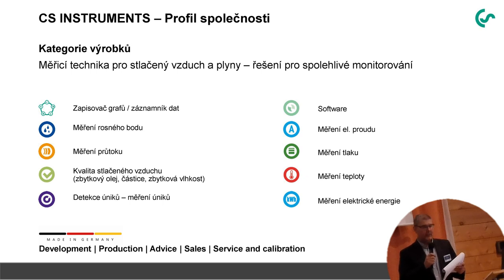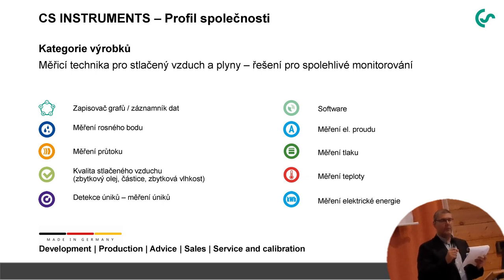Then we have the dew point measurement. We offer the flow measurement. And one big topic in compressed air is the compressed air quality. Most of the factories are interested in their compressed air quality. That means residual oil measurement, how much oil is in the compressed air, how many particles are in the compressed air, and what is the moisture in the compressed air. And further on, we also offer leak detection and leakage measurement. On the right side, you can see that we also have accessories, for example software solutions, current measurement, pressure measurement, temperature measurement, and electrical energy measurement.